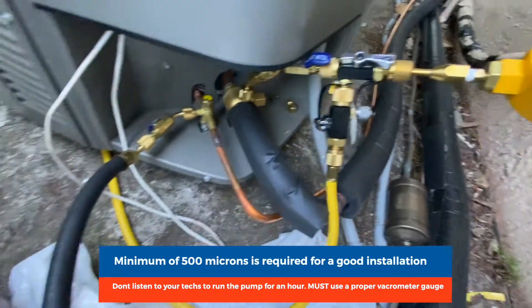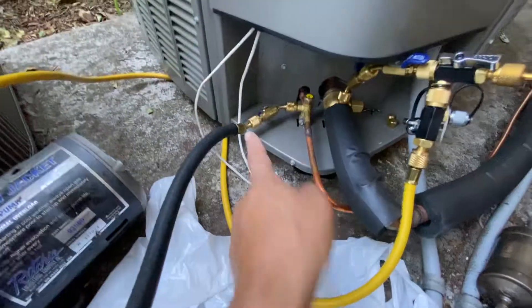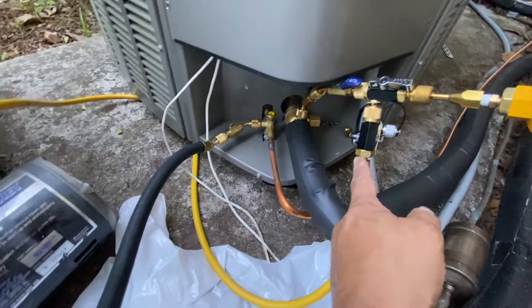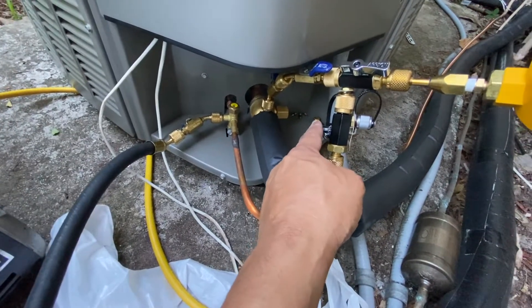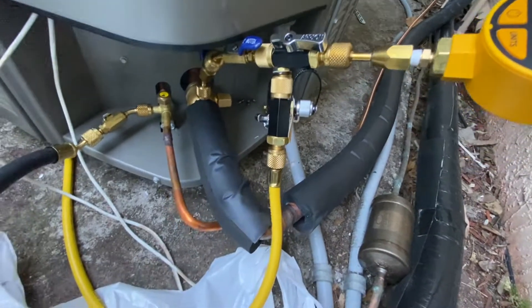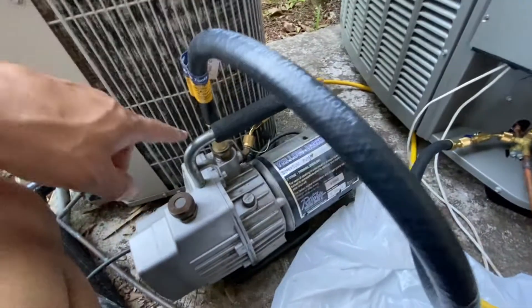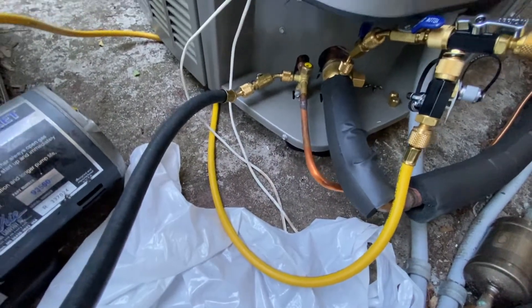This is my final setup. I had to move the black hose over here — I think it works better this way. For some reason when I left that valve on it was vacuuming out pretty fast, but when I turned it off to measure on the gauge it was giving me oddball readings. So what I did was turn that side off and I only pulled the vacuum from the top side, from this one. It took a while because of that.